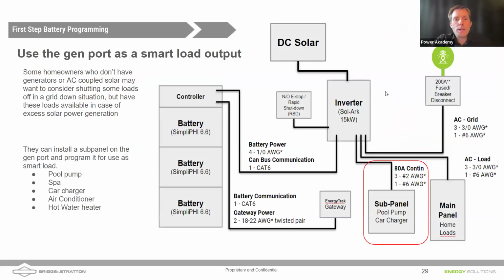So we're going to jump into programming outputs now. We're going to talk about using the generator port as a load output. You might want to do this if you have a load that you don't necessarily want to back up. So you've got a load such as a hot water heater that, if you lose electricity, should stay warm for a while, and you don't necessarily want to be using battery power to keep that water topped off. You don't want to keep a pool pump on, right?